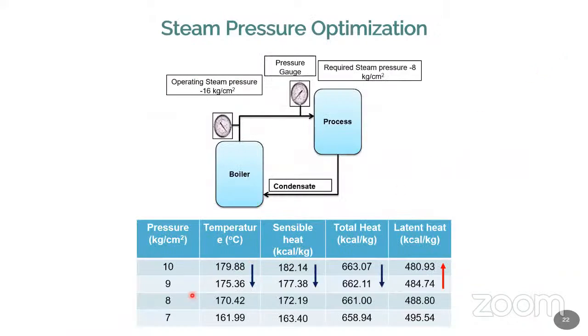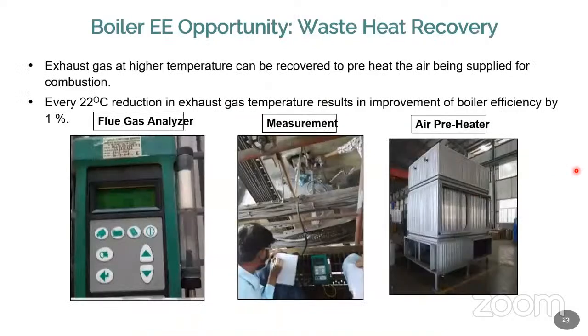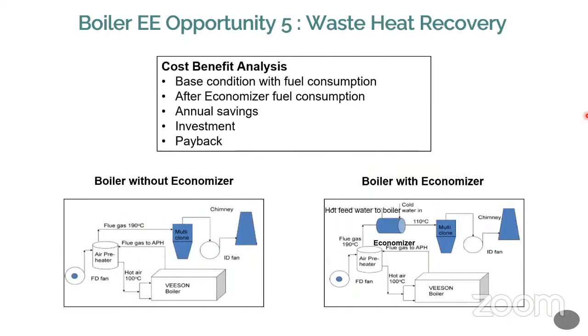Then steam pressure optimization. If you are operating the pressure at a nominal level, then you will have very good savings in the systems. Then you can measure the flue gas at the flue gas point, and if the temperature is very, very high, then you can reduce the temperature either by using an air preheater, water preheater or economizer, and you can optimally load the fuel. That will also have a very good impact. For every 22 degree reduction of your flue gas temperature, you save 1 unit of fuel in the system. Then you have good savings in the economizer. I told you, almost 99% of the boilers will have an economizer.